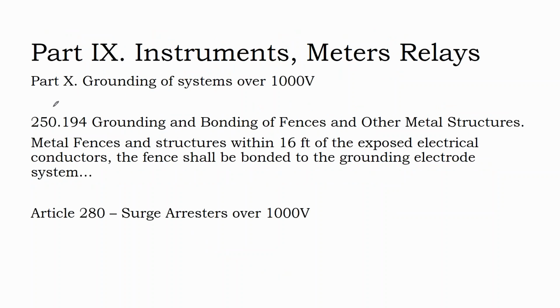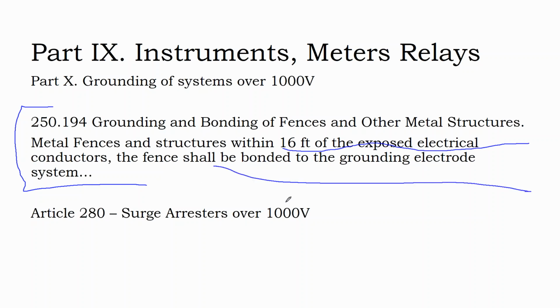Now this is for you ground mount utility scale guys. Metal fences and structures within 16 feet of your array need to be connected to your grounding electrode systems. Once you get into higher voltage systems, the higher voltage you go, the more that electricity is going to be impacting the voltage of the immediately surrounding earth, and more likely it can arc out over longer distances.